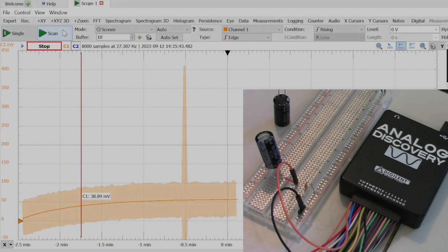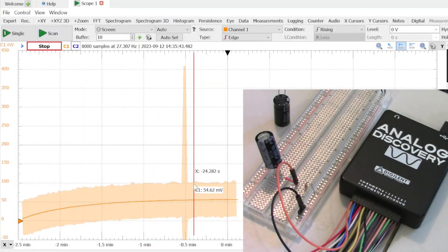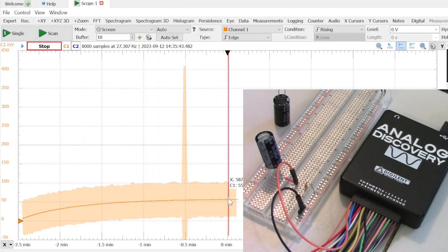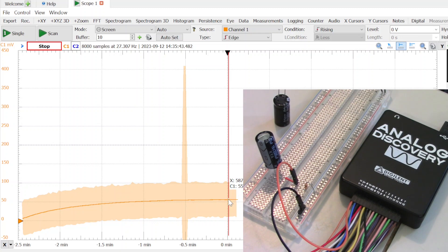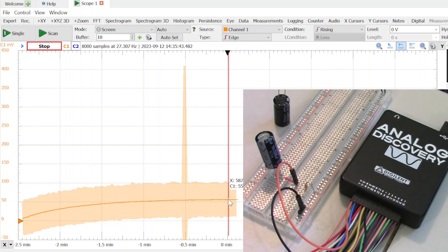I'm going to go ahead and stop it there. So here we are, two and a half minutes later. We're at 56 millivolts into 10k, which gives us approximately 6 microamps, which is considerably better than the 530 microamps, which was considered maximum for this particular capacitor.